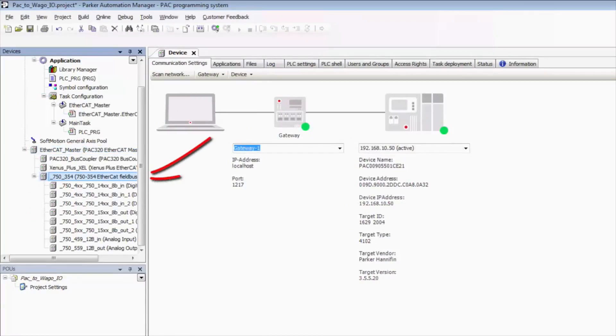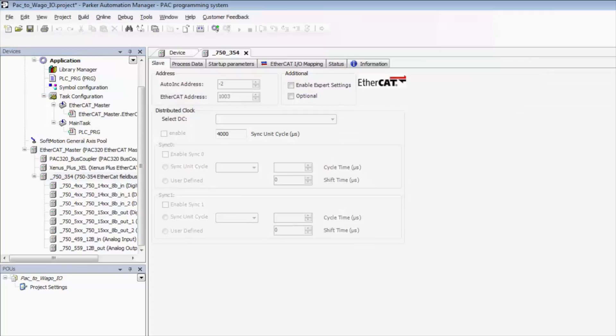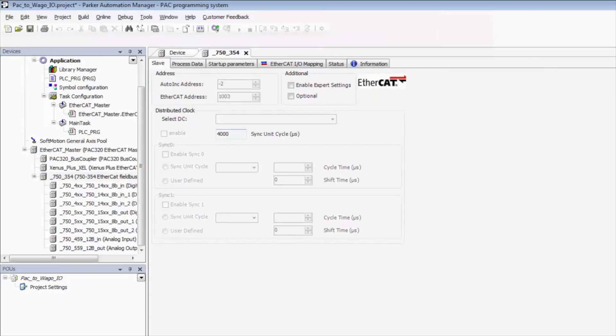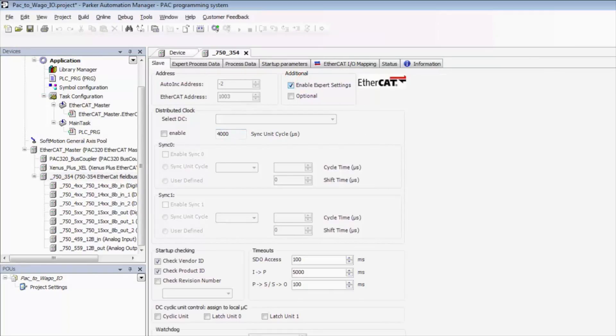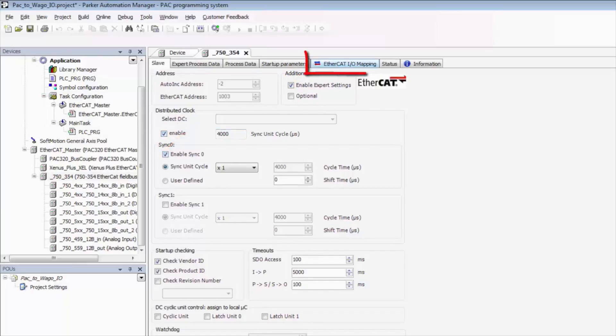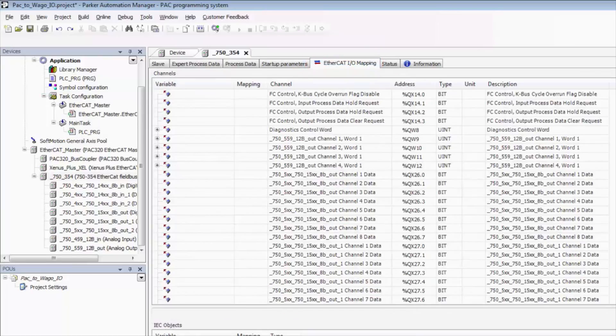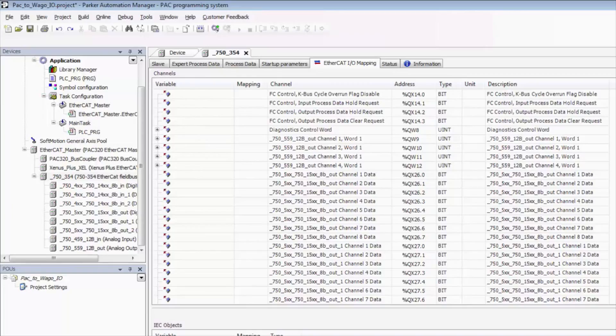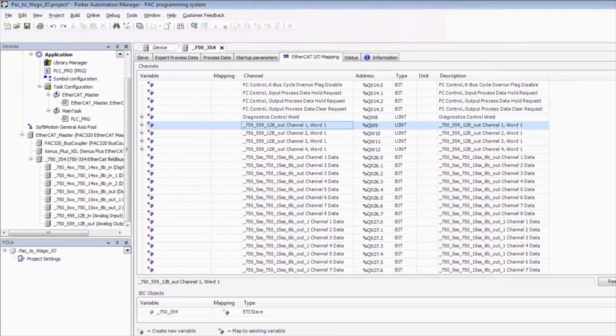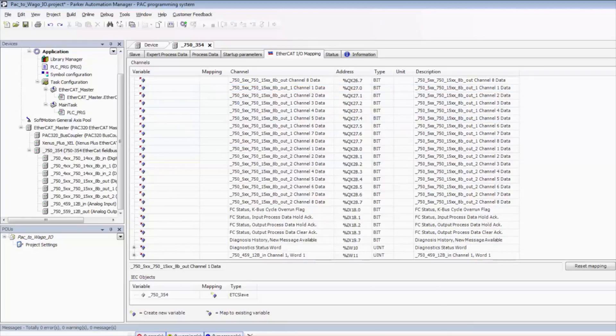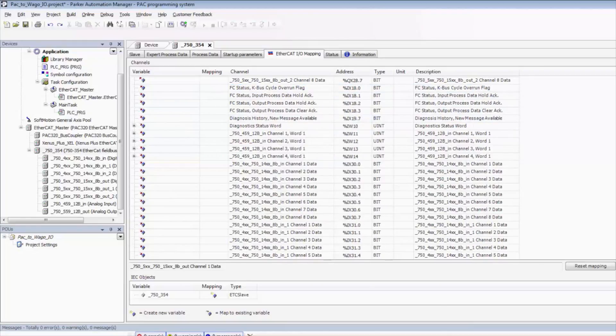Next we need to double click the IO itself. We need to click enable expert settings. We'll need to enable the distributed clock and we're going to have to enable sync zero as well. Underneath the EtherCAT IO mapping, we can see that we've got all of our modules here including our outputs and our digital inputs.